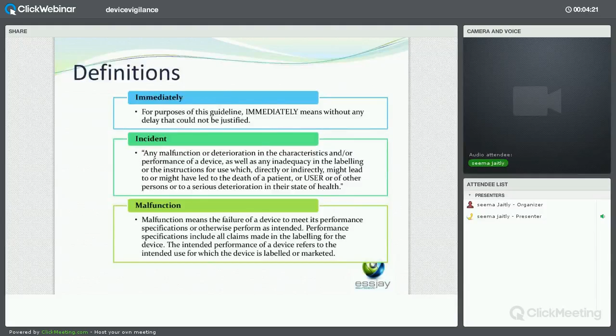And it could also be down to something that could have happened due to inadequacy of the labeling or instructions. And as I said here, they talk about the direct or the indirect. You've got the malfunction as well, where there's a failure of a device to meet its performance as intended. So if you think about what a device is, it's not working as you would have expected it to work. And then we've got serious public health threat. A bit similar to, say, an emerging safety issue. We've got a similar situation with medicinal products.